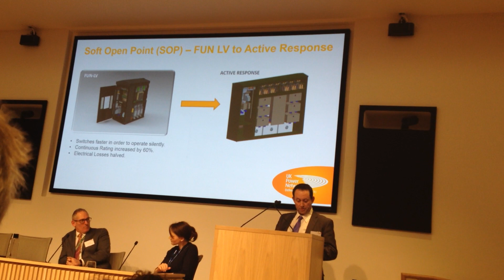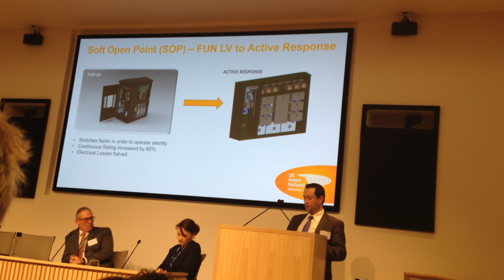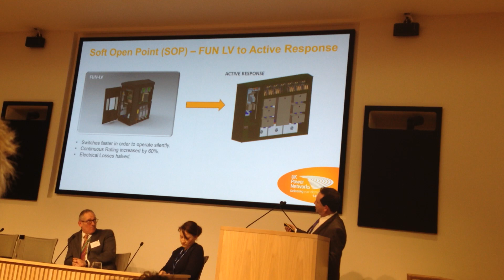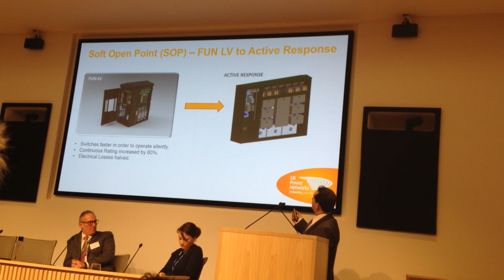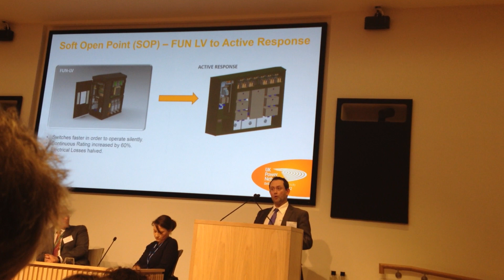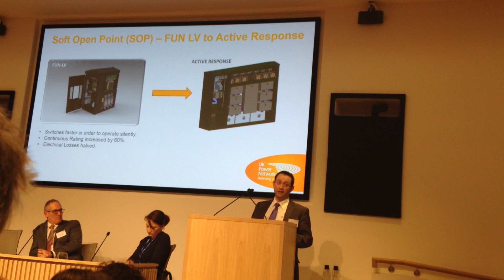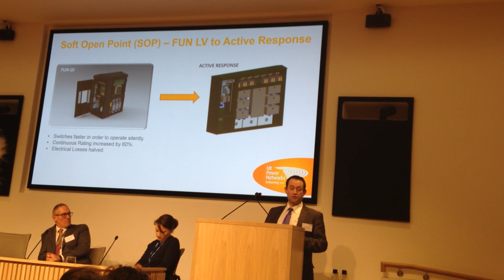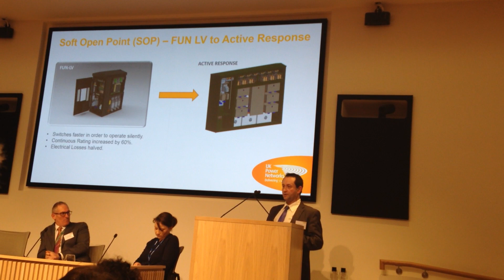We've got two things we want to address with the architecture itself. First, this device on the right-hand side is a lot more efficient. These are the reactors - if I switch at 5 kHz, those reactors are very big and produce a lot of heat. These are the reactors on Active Response; they're a lot smaller, so we generate a lot less heat, lower losses. In this system we were generating about 12 kilowatts of heat - that's a lot of heat, and we need a lot of air to shift that amount of heat. Moving to this particular system, we reduce the losses to something more like 5 kilowatts. We don't need to move so much air, and the system becomes a lot quieter.